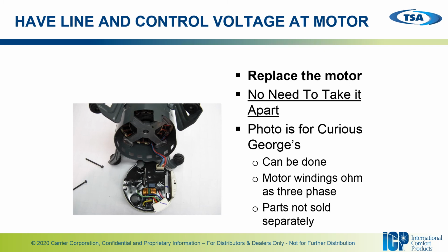But just like the variable constant airflow motor, your motor is a three-phase motor, so your windings are going to ohm out as a three-phase, so that means they should be very close to equal, within 10% of each other, and you would ohm them out for shorts to ground just like you do the variable constant airflow.